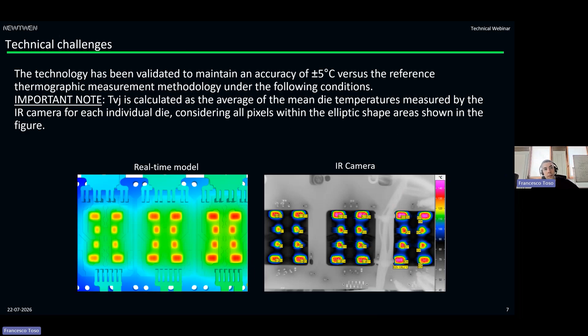Then we have the latest challenge we are going to solve: faulty conditions. We also have extreme conditions we would like to address, that our model has to predict with high accuracy. I'm talking, for instance, about coolant fault. So when, for example, in your inverter the pump of the cooling system is in fault, the coolant flow is not flowing anymore, the speed of the coolant is 0, and you have a completely different behavior compared to when the coolant flow is at the nominal flow rate, or even in the worst case, the dry operating condition. For instance, a loss in the pipe of the coolant, and now the cooler of the inverter is completely empty, you have air inside, and once again the thermal behavior will be completely different with respect to the nominal condition. So these are the 4 challenges that we are now going to tackle. Let's see how the model behaves.